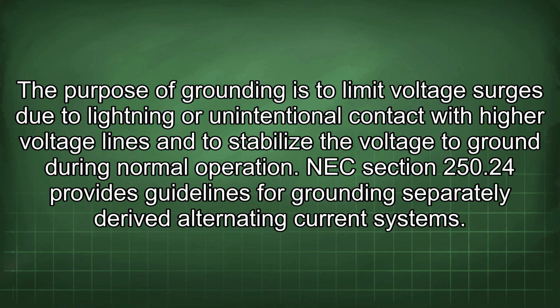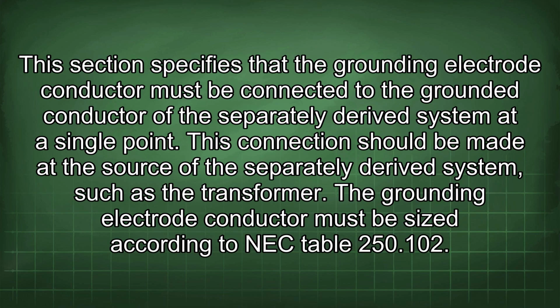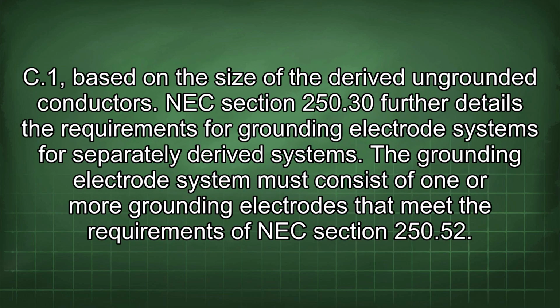NEC section 250.24 provides guidelines for grounding separately derived alternating current systems. This section specifies that the grounding electrode conductor must be connected to the grounded conductor of the separately derived system at a single point. This connection should be made at the source of the separately derived system, such as the transformer. The grounding electrode conductor must be sized according to NEC Table 250.102(C)(1), based on the size of the derived ungrounded conductors.